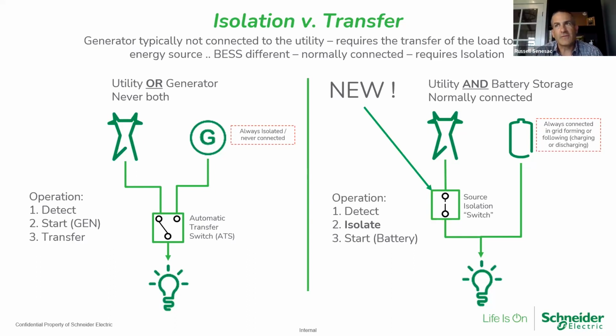I think the major difference now is that a battery energy storage system behaves differently. A battery energy storage system is normally connected to the load and to the grid, and that's not true with generators. Generators are typically never connected, I won't say never, because there are unique corner cases where somebody wants to do peak shaving or something like that. But in normal operations, the bell curve, you don't connect them.